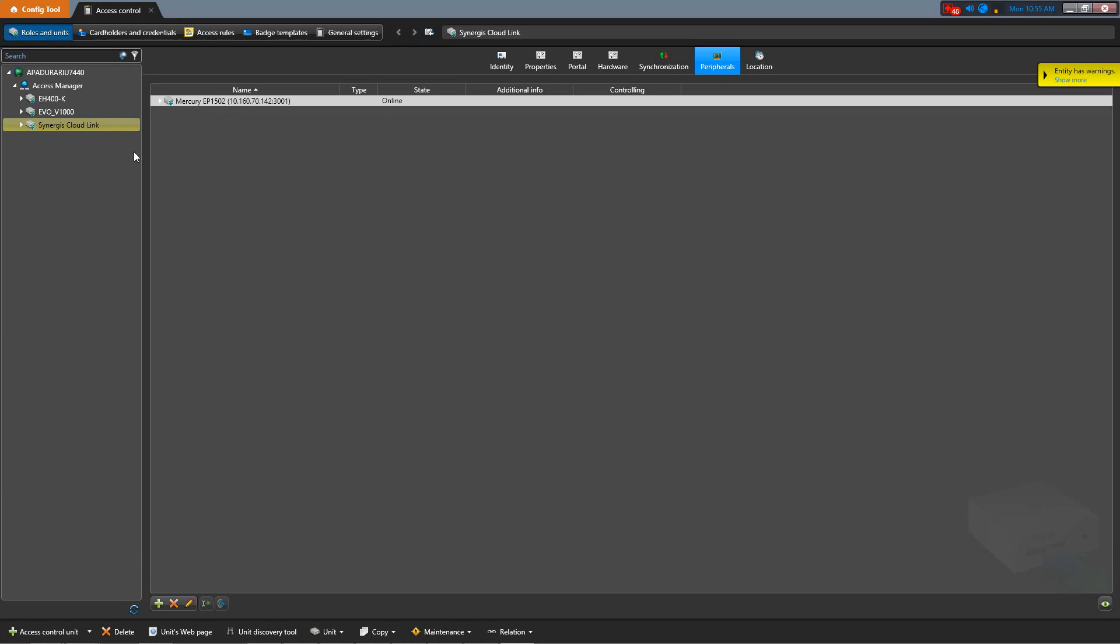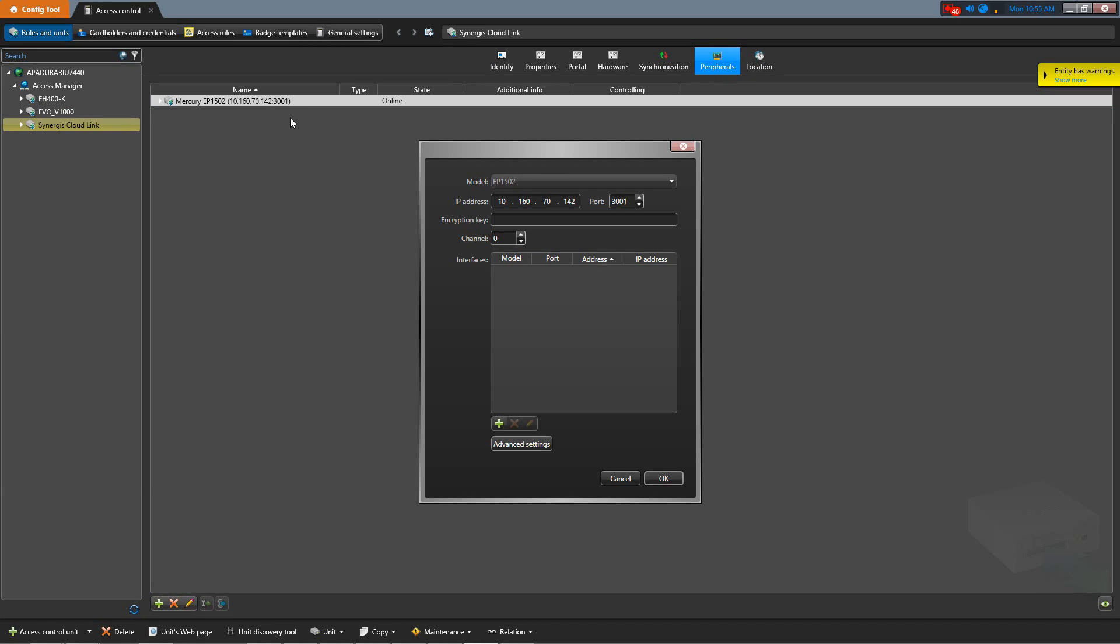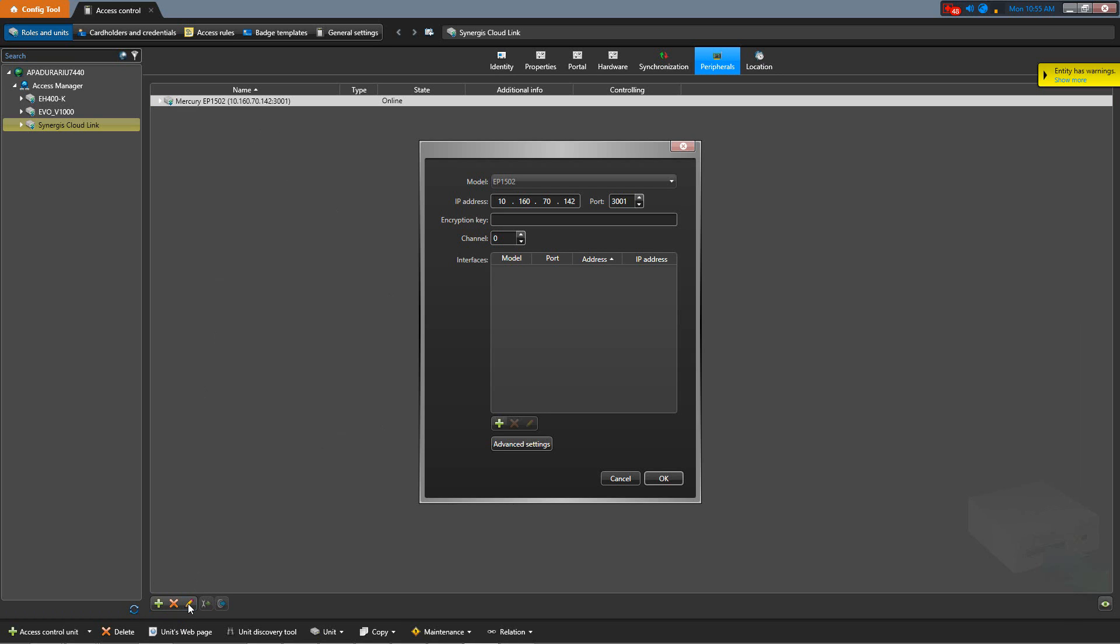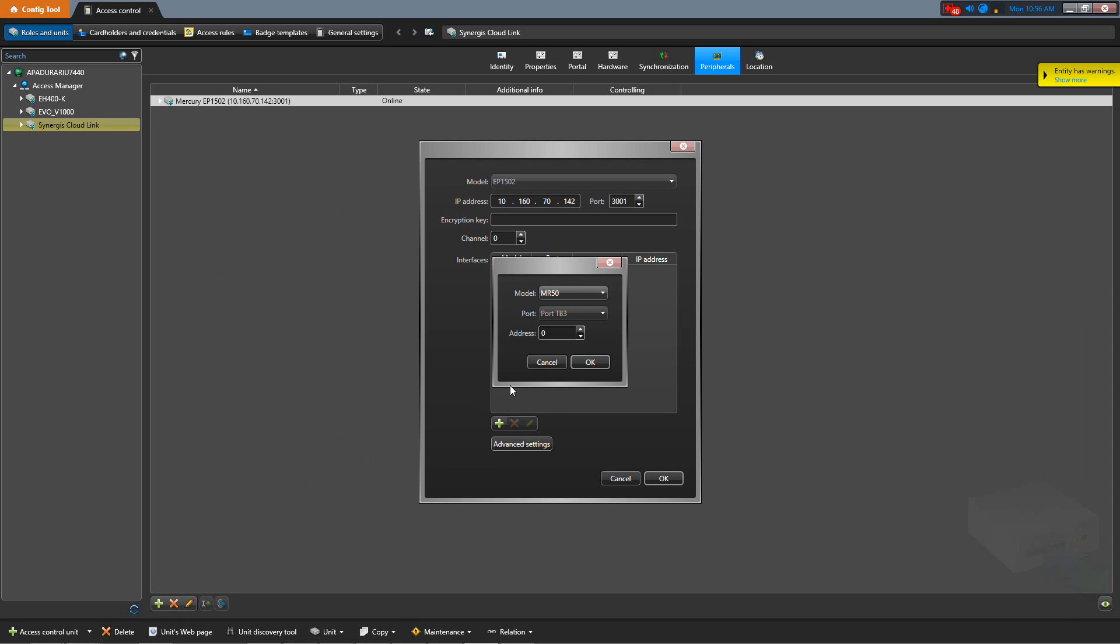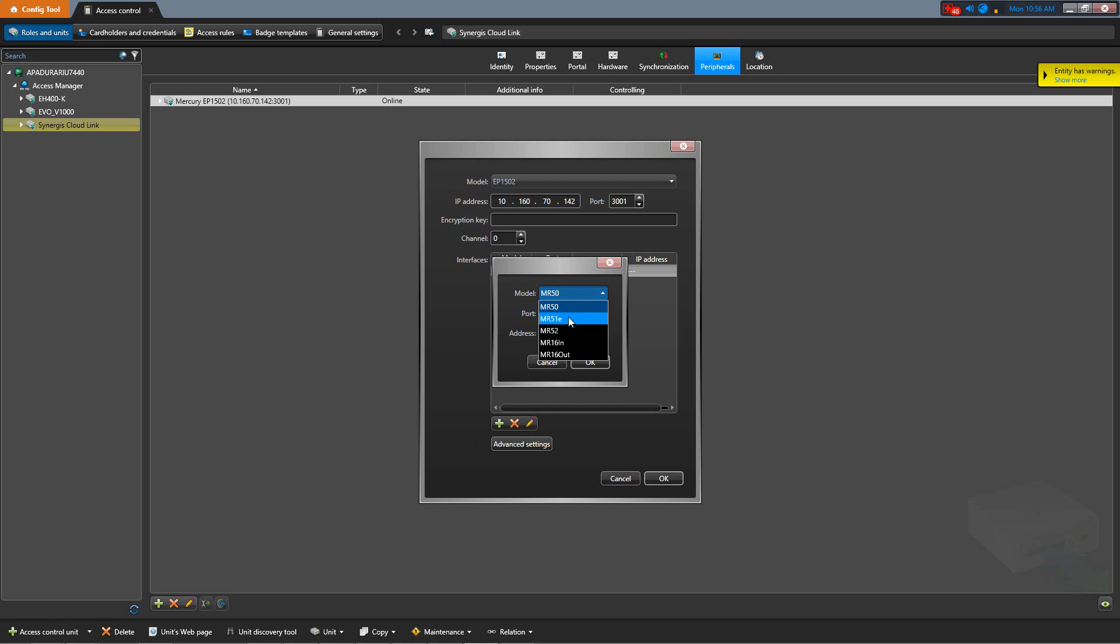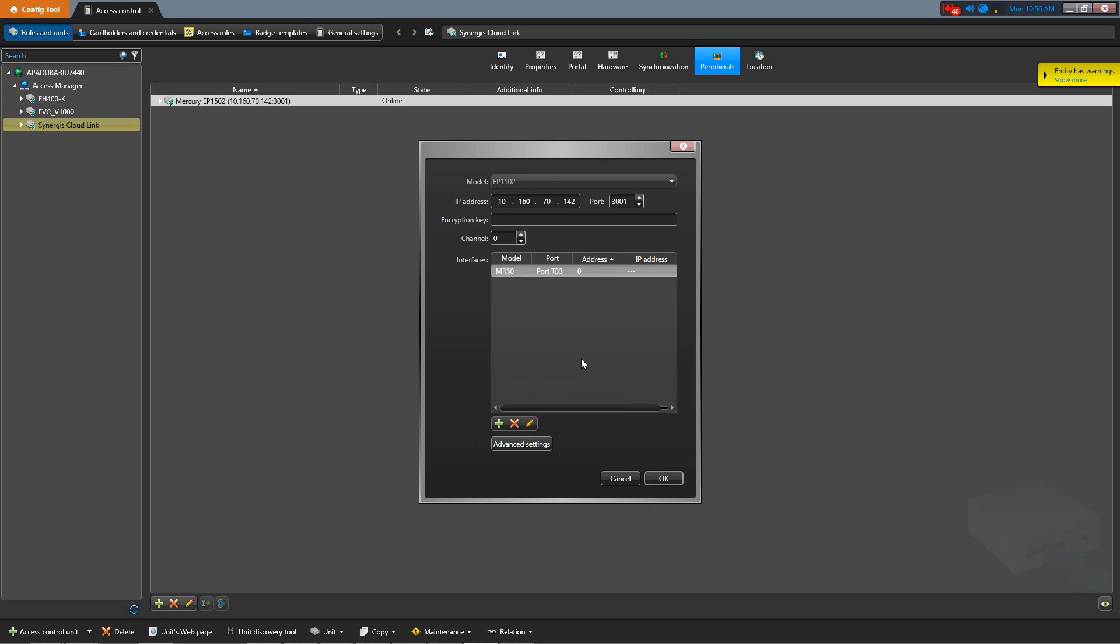We begin by either double-clicking on the Mercury EP1502, or by clicking the Edit button while the EP1502 is selected. We then click Add an item. Our first panel that we want to add is the MR50, which is on address 0. We click OK, we click Add an item again, and now select MR52 from the drop-down menu, and switch the address to 1, since our MR52 is addressed 1. We hit OK twice, and then Apply.